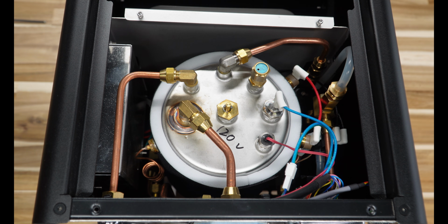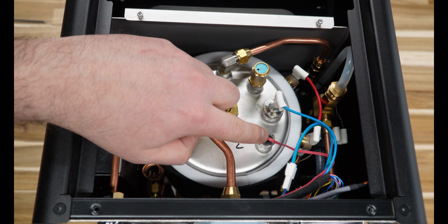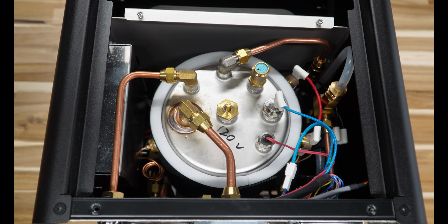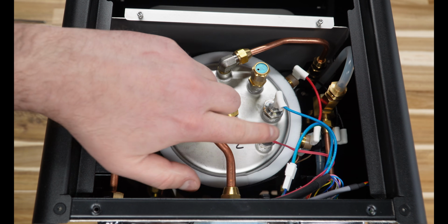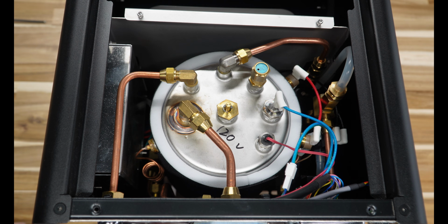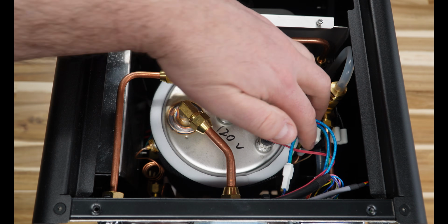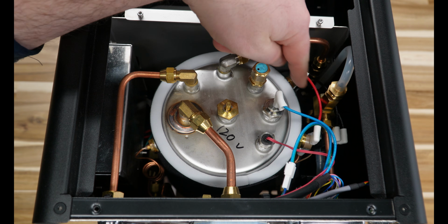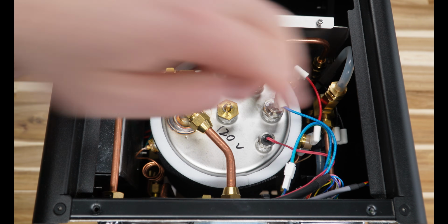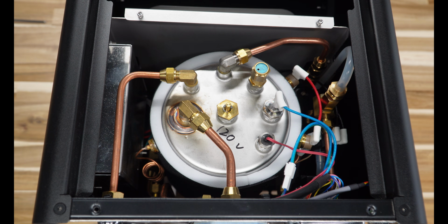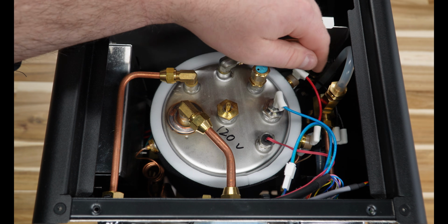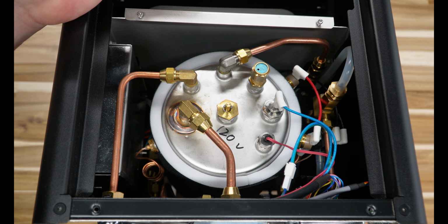We showed in a maintenance video recently how to test some of these components. I can actually link that below, but that is where your temperature probe is going to be for your PID display in the top. We'll show a better view of it here in a second, but we do have some thermal overloads on the side. It's these red wires through here. Really all those are there to do, if for whatever reason your machine got really hot again, is to interrupt the circuit, essentially a thermal circuit breaker, to turn off your boiler so that you don't ruin your machine or get hurt.